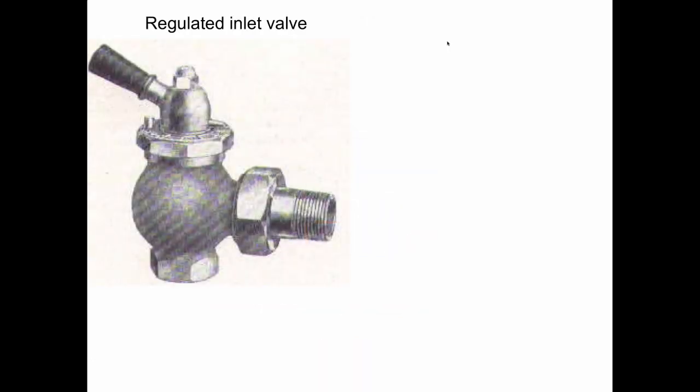So don't get sucked into that. Also note too that if you see these old style radiator valves that had little pins on them that you see here, and they had these markings on the top, they were cast into the top markings. And what you need to know is that every one of those markings represents 10 square feet of EDR. Because this radiator valve has an orifice built into it that's variable. So depending how much you opened it, it would be able to allow in only as much steam as the radiator would condense. And the installer back in the old days would peg the radiator at that point. And because he did this, this radiator is not going to have a trap.